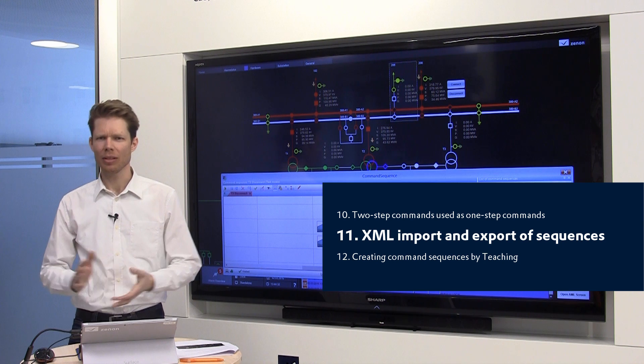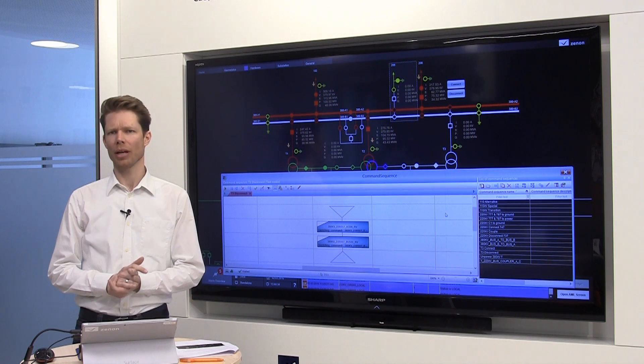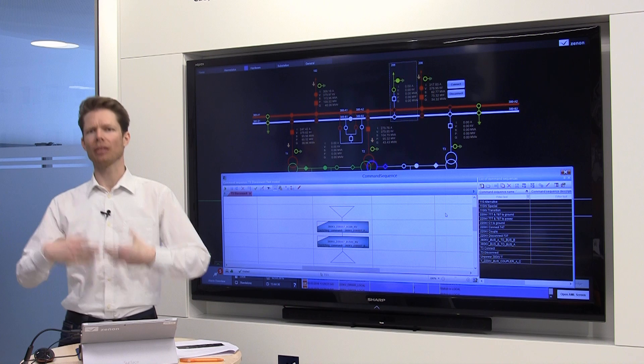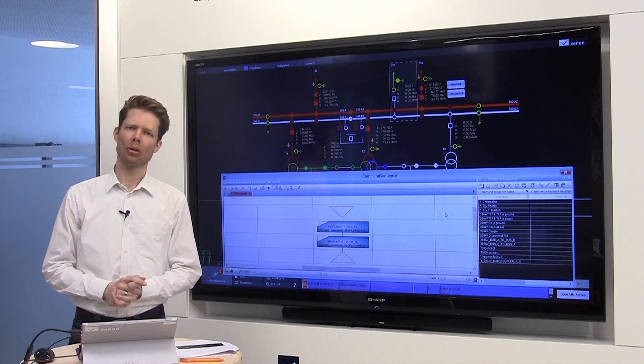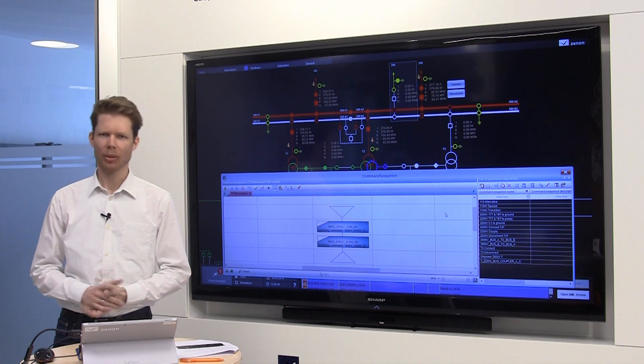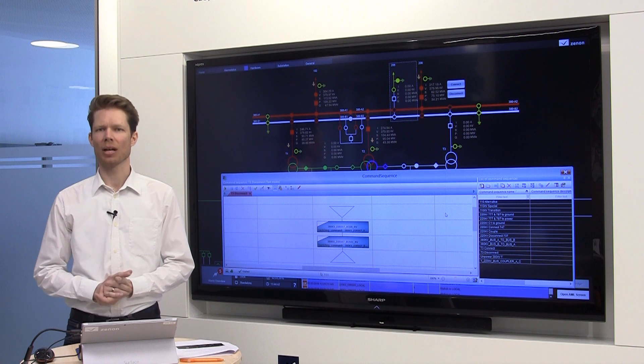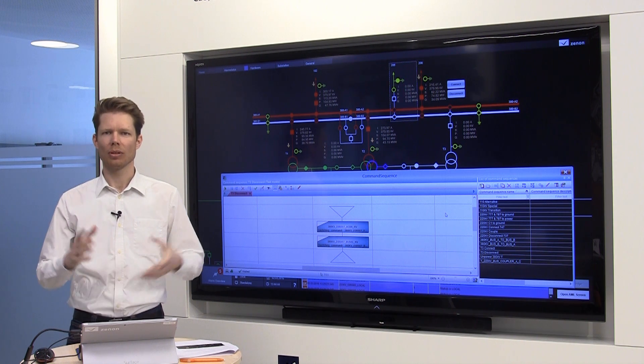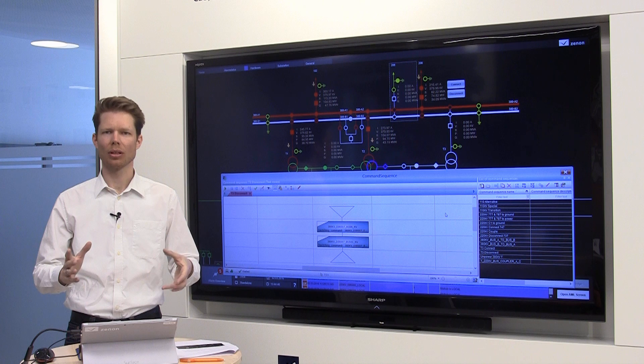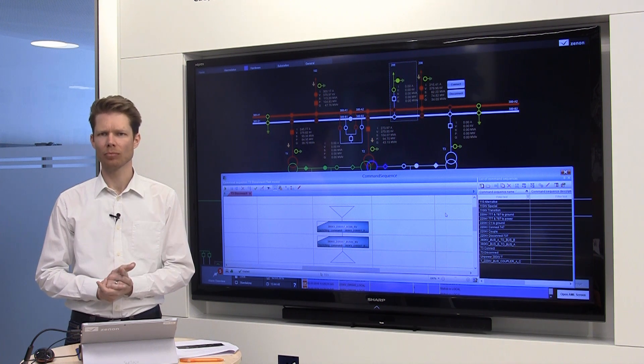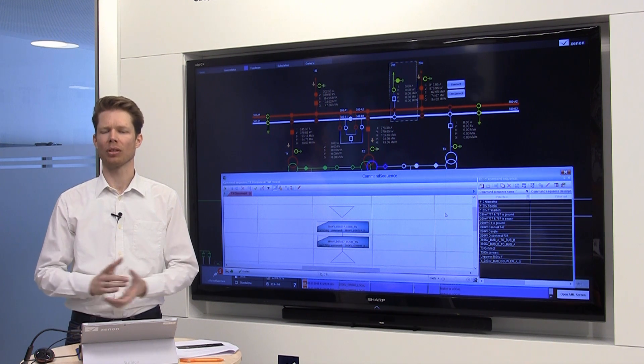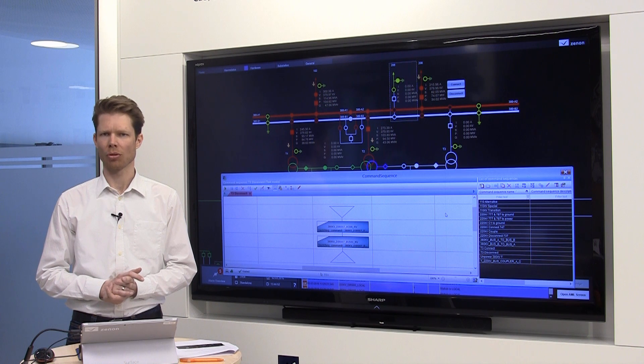If you want to reuse a command sequence or you prefer to create it offline in your office and then import it into your operational system, this is no problem with the zenon command sequencer. You just take your sequence, export it into XML and then re-import it at the controller station.